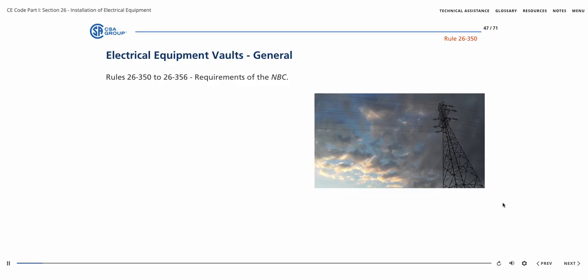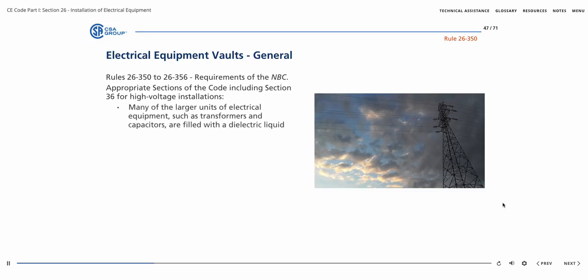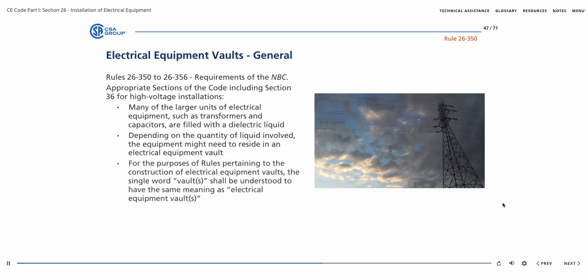Requirements of the NBC and other appropriate sections of the Code, including Section 36, for high-voltage installations are outlined in Rules 26-350 to 356. Many of the larger units of electrical equipment, such as transformers and capacitors, are filled with dielectric liquid. Depending on the quantity of liquid involved, the equipment might need to reside in an electrical equipment vault. For the purposes of rules pertaining to the construction of electrical equipment vaults, the single word vault or vaults shall be understood to have the same meaning as electrical equipment vault or vaults. Vaults shall not be used for storage purposes.